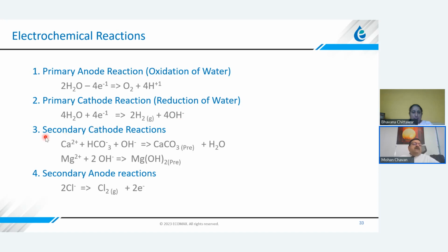Then we have a third reaction called the secondary cathode reaction, where calcium bicarbonates will react with OH- ions at the cathode to precipitate calcium carbonate, magnesium hydroxide, magnesium carbonate. So in the form of these compounds, these calcium and magnesium ions will get precipitated. And along with this, even other elements are getting precipitated on the cathode. I'll show you the analysis in the next few slides. Like silica also is getting removed.